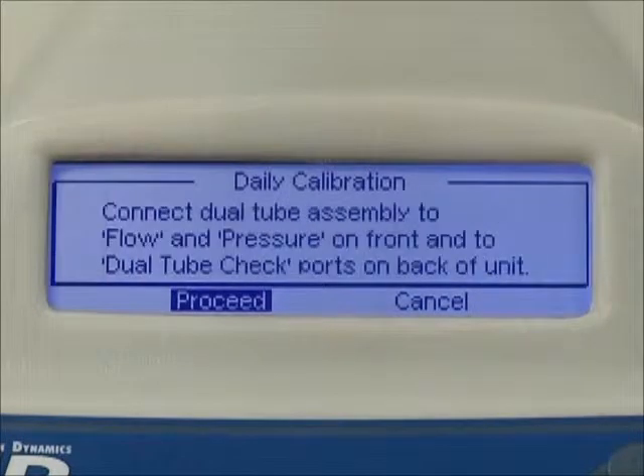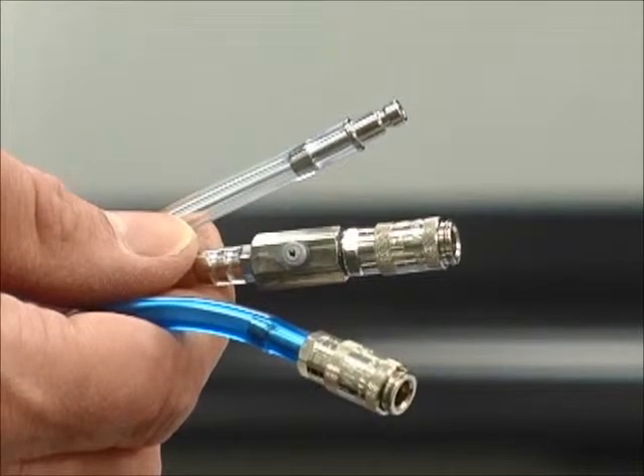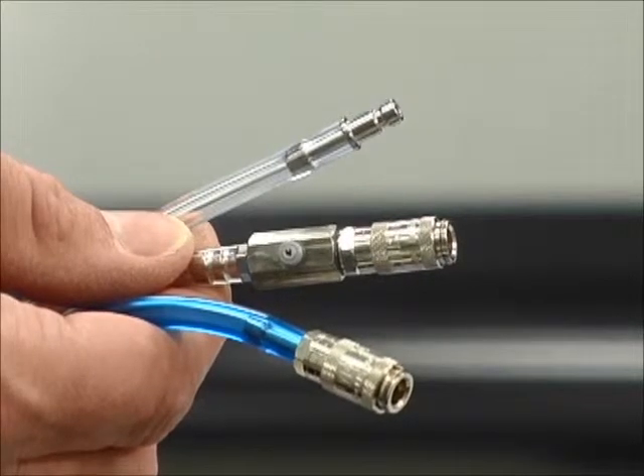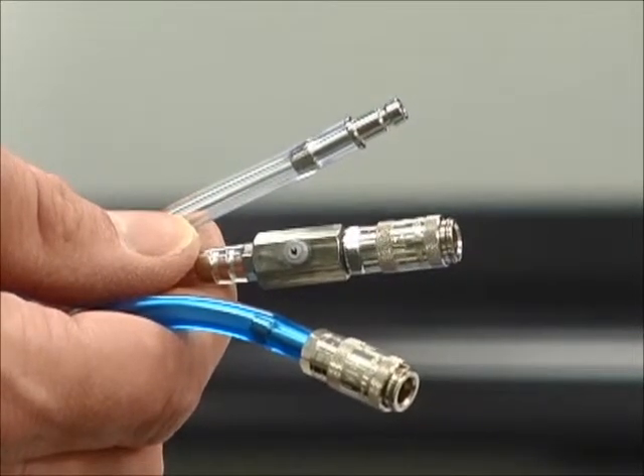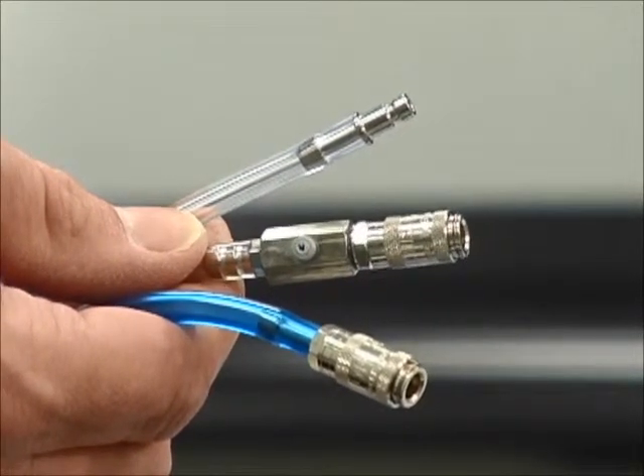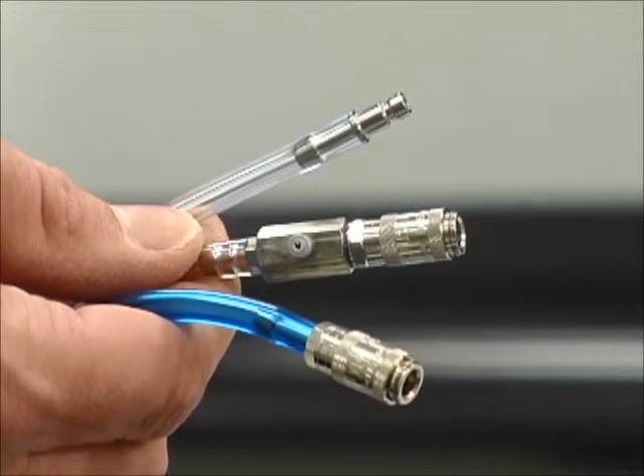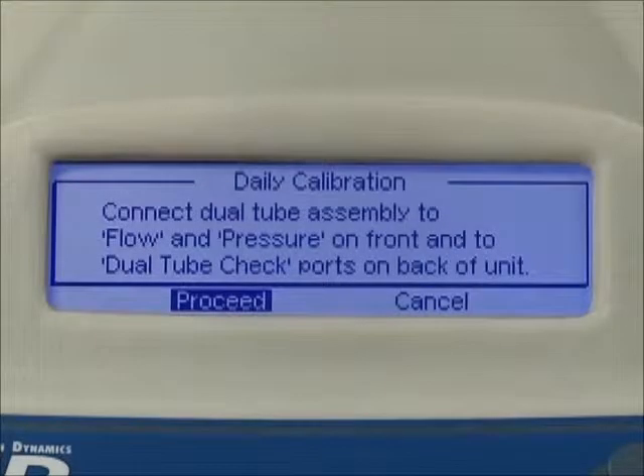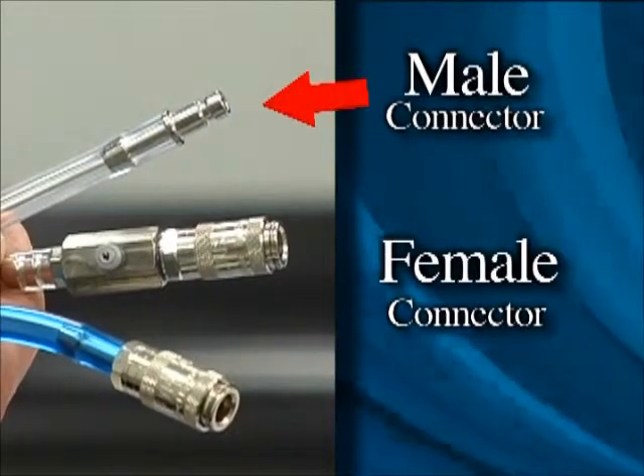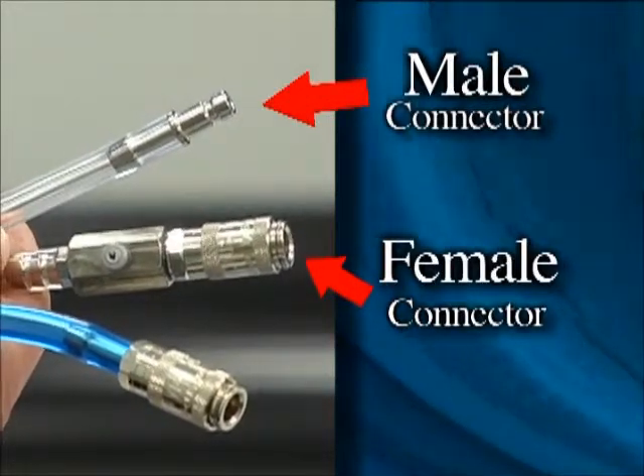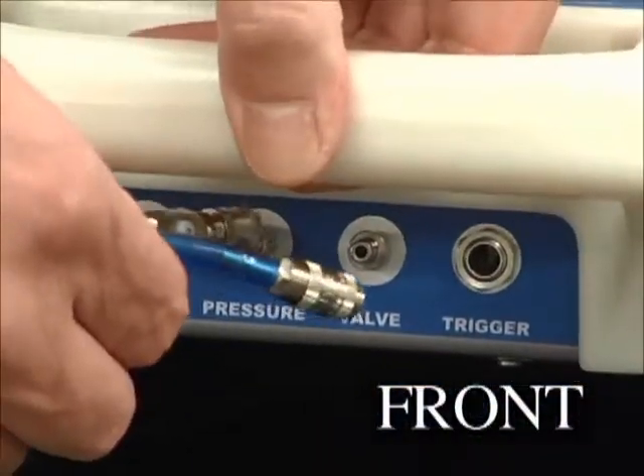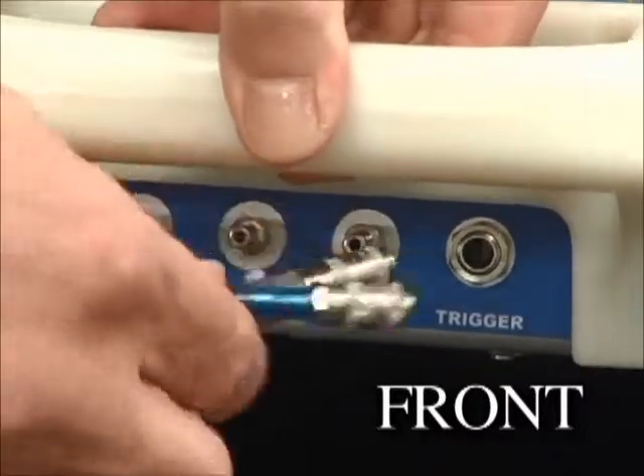Once the unit is zeroed, the next step will be a dual tube calibration. You'll notice there are 2 clear tubes and 1 blue tube. The 2 clear tubes are a part of the triple tube assembly, and these are referred to as the dual tubes. The screen will prompt you to connect the dual tubes to the front and back of the Quantifit. One end of the dual tube has a male and female connection. These will be connected to the flow and pressure connections on the front of the unit.